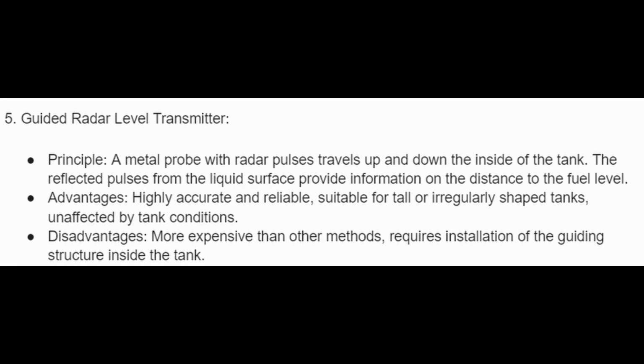5. Guided radar level transmitter. Principle: a metal probe with radar pulses travels up and down the inside of the tank. The reflected pulses from the liquid surface provide information on the distance to the fuel level. Advantages: highly accurate and reliable, suitable for tall or irregularly shaped tanks, unaffected by tank conditions. Disadvantages: more expensive than other methods, requires installation of the guiding structure inside the tank.